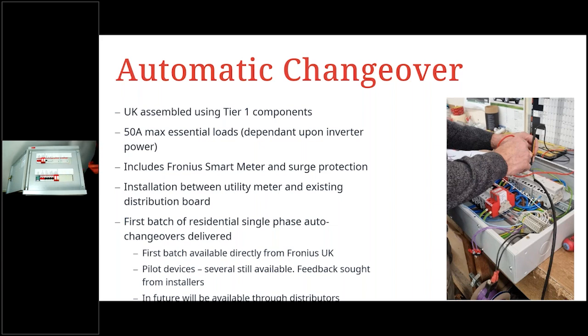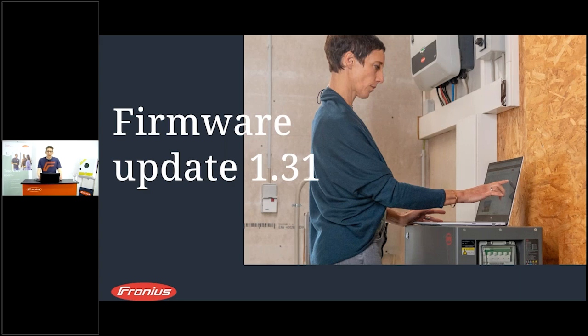We then have the connection for the Gen24 and also for the surge protection there for the incoming power from the Gen24. We have two sets of contactors there, so we have redundancy. If we have one contactor fail, the second one will still operate and put you into island mode. And also behind here, we have our digital input signal connections. So everything is in one box.